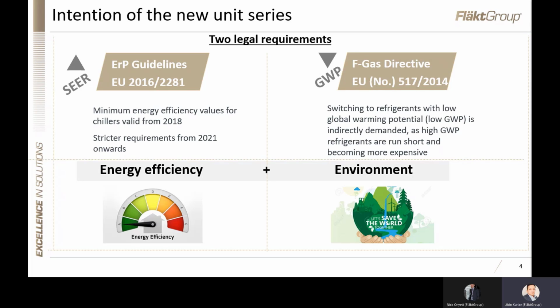The second requirement is related to the F-gas directive, which is directly related to the environment and demands the use of lower GWP refrigerant. GWP stands for global warming potential.